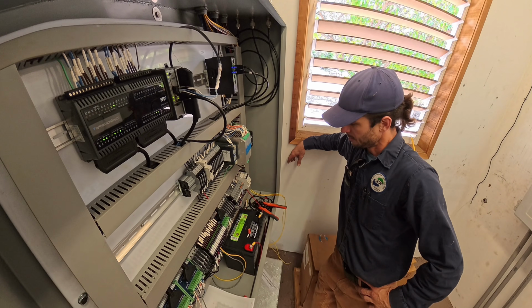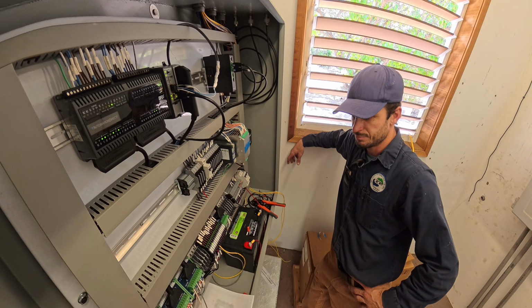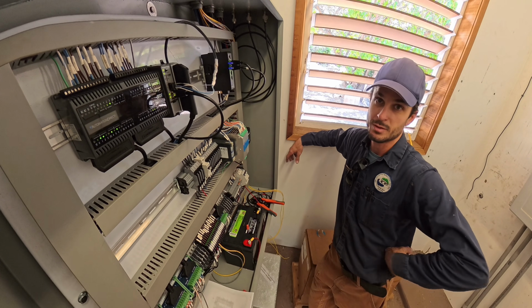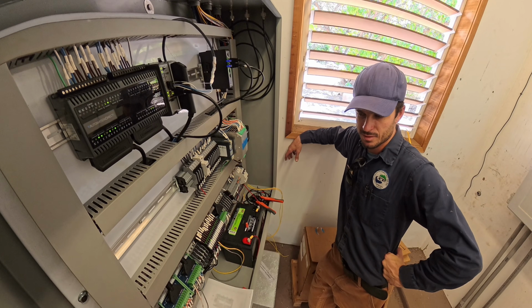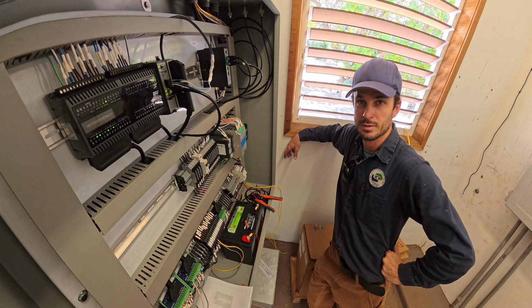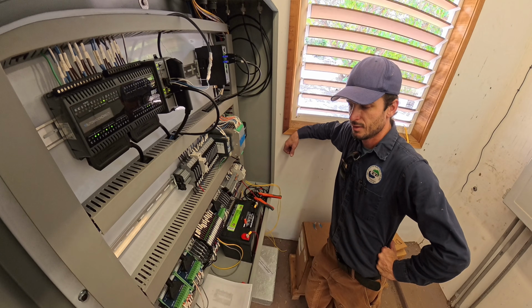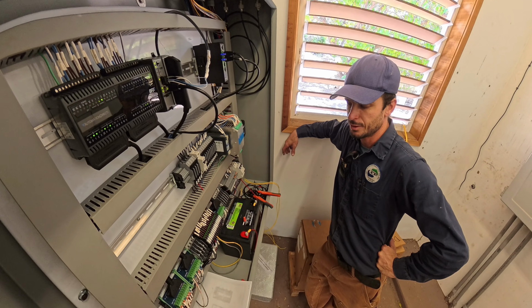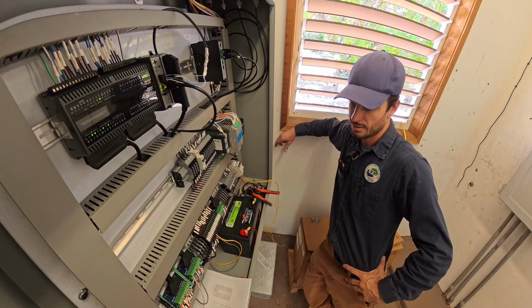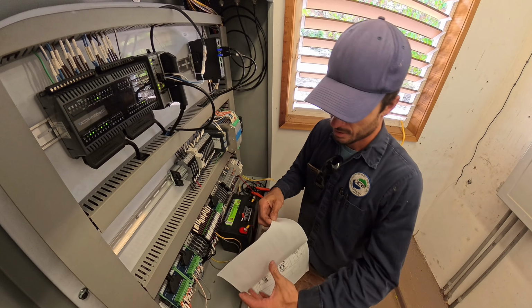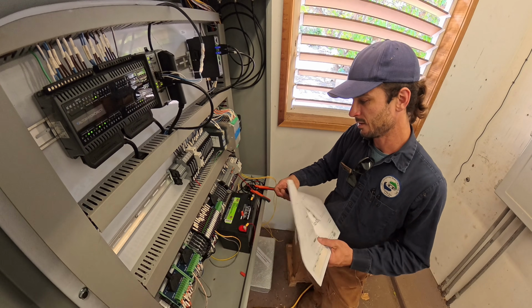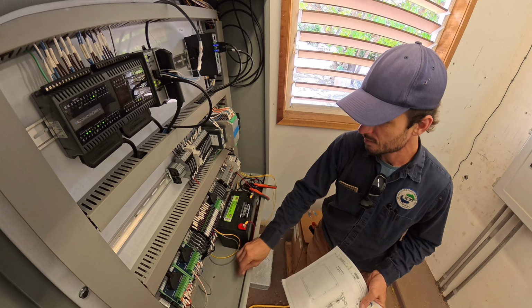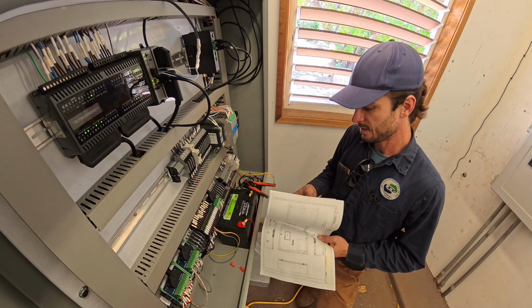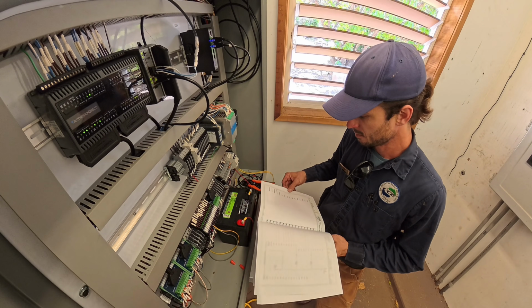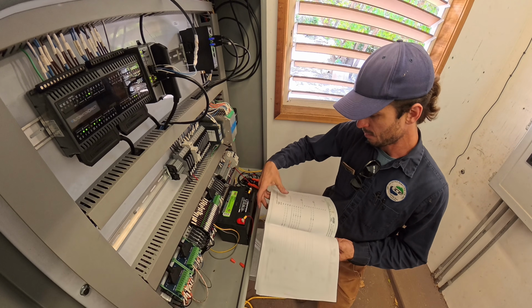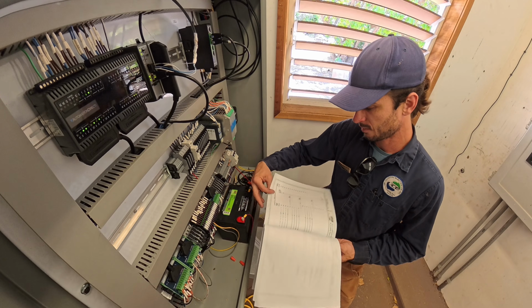Well, now that I've got the pairs in here, and just looking at my PLC and my input blocks, I'm not seeing any spare digital inputs that I can land this on for the float switch. So I'm going to take a look at the wiring diagram, see what they are, and we may have to sacrifice one that's not as used temporarily in order to gain this feature. So let's see here, there's relay outputs, here's the digital inputs.